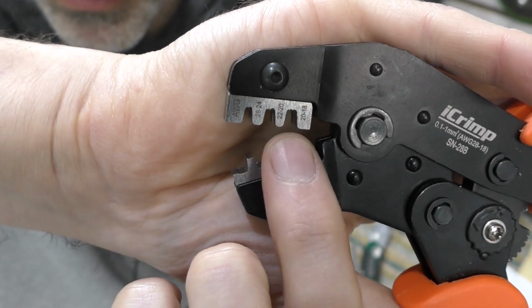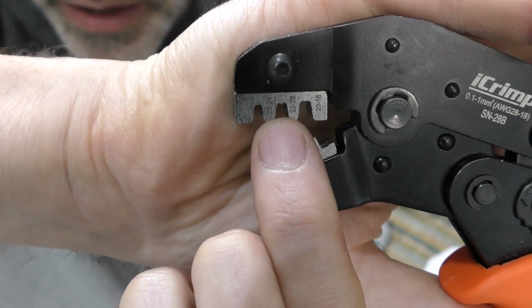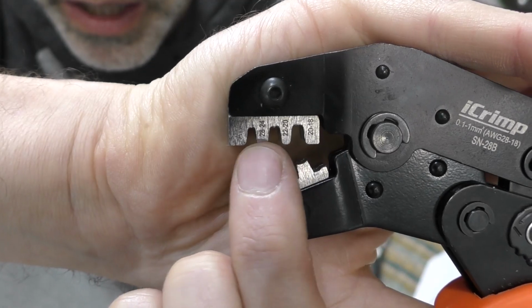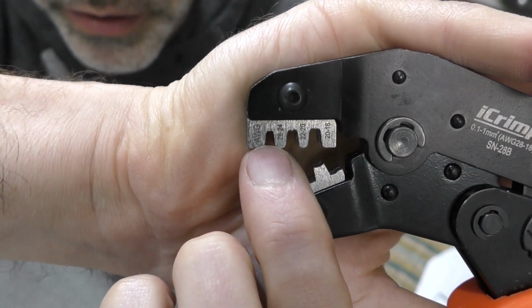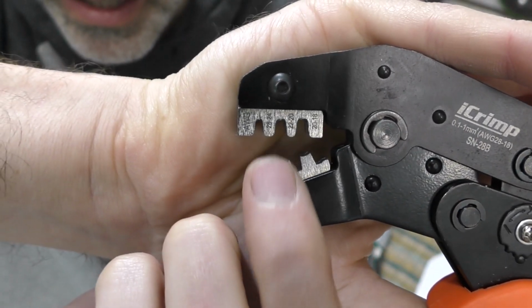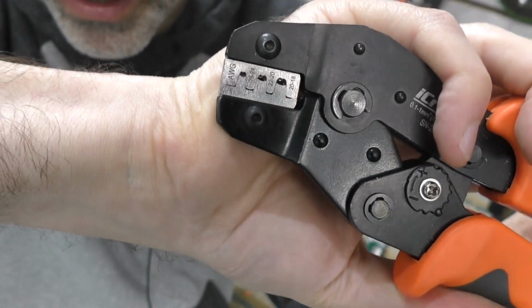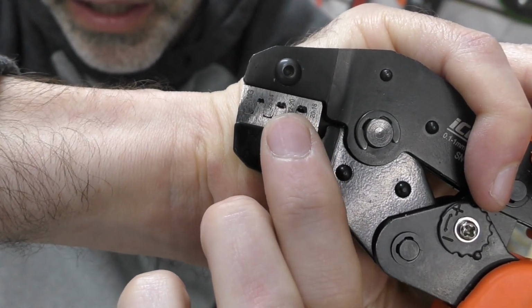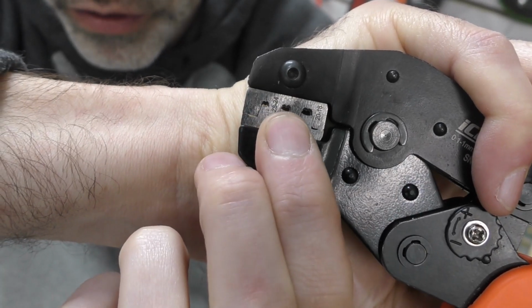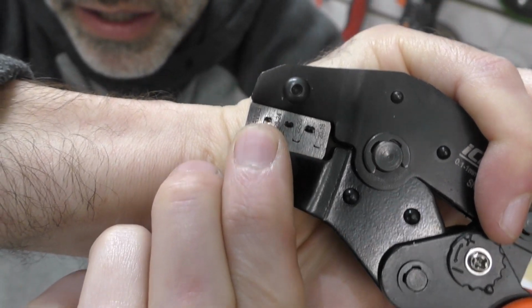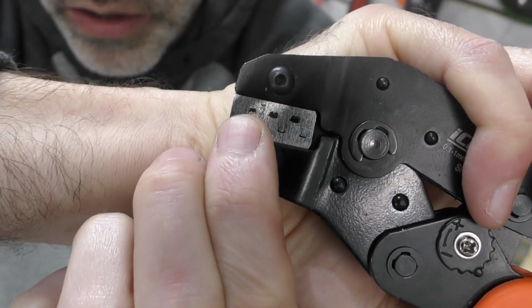Notice you have 3 different jaws here, all based on wire size: the middle one being 20 to 22 gauge, and the furthest forward one for 24 to 28 gauge. When I close the jaws, you'll see a definite width difference between all 3, so once you're done crimping that pin, it's going to be one of these widths.